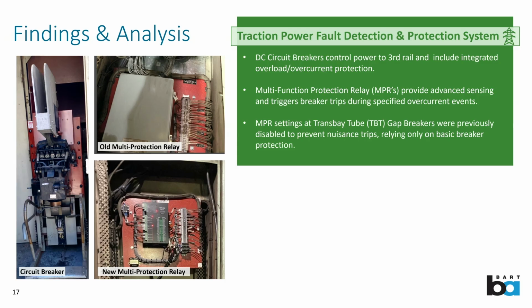Further RFIs were submitted asking why they were disabled, and the reason provided is that they were nuisance tripping in the morning upon return to service. There was apparently nuisance tripping which impacted being able to run cars consistently every morning, so we found that they disabled these to make sure trains were running smoothly.